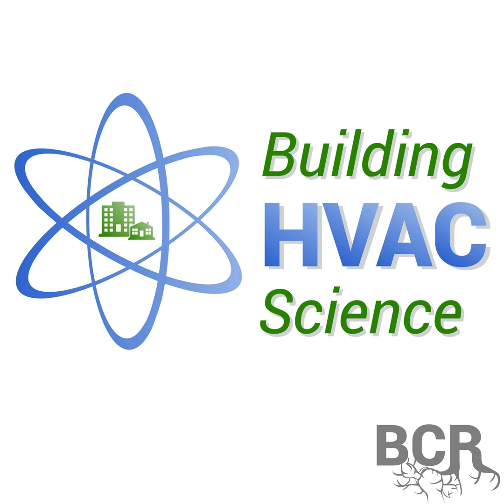Think about air quality within a controlled system or space. We have a data logger that can record temperature, relative humidity, and CO2 within an area, something controlled by an HVAC system. Think of a bullpen of people working all day, and every day around 2:30 everyone starts getting sleepy and productivity falls off, and we don't know why. One reason could be a bad air mixture coming in, not enough fresh air into that space. This is a great indicator to understand the temperature, the relative humidity, and the CO2 level. CO2 can make you sleepy, and if it's too high and you're not getting enough fresh air into the space, you need to do something about it. This gives an HVAC contractor the data to decide how much fresh air should come in, whether to open the dampers more, and how to get more air into the space to keep CO2 levels down.